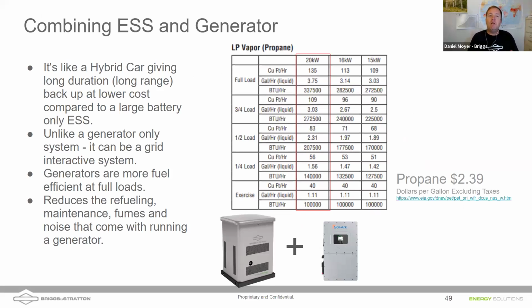I think this is worth at least one more minute here, although we've just run out of time. When you run a generator at a lower load point, you're not really getting the same miles per gallon out of that generator. If you can run the generator hard, run it hard, charge the batteries, support the loads, and then shut the generator off, you save fuel, you save the noise, and you save maintenance on the run hours. It's like driving a hybrid car. So I think that's kind of the key takeaway for everybody.